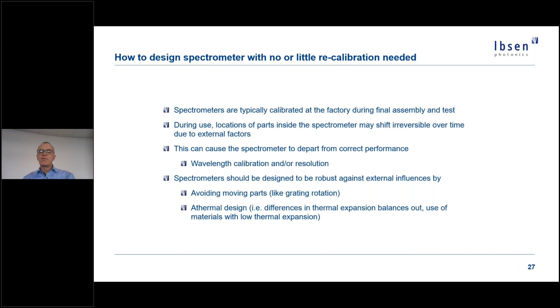So to avoid this, we need to design the spectrometer such that the internal parts remain at their original position under various external influences like changing temperatures, mechanical shocks, etc. In general, moving parts are a no-go because they will wear over time and unavoidably need recalibration or even replacement. Also, it's possible to use materials with lower thermal expansion or use materials in a smart way where differences in thermal expansion balance out.